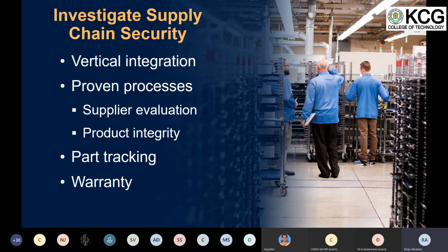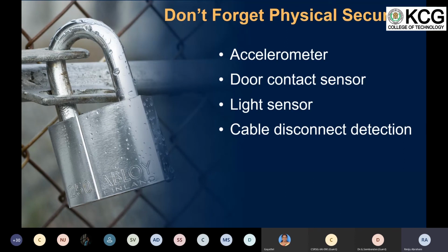Apart from the cybersecurity of internal devices, we should also follow physical security, like the perimeter, the physical fencing and all, and accelerometers in the devices. There are devices which have an inbuilt accelerometer, door contact sensor, and light sensor. These can detect such things and alert the operator or the engineer, and an alarm can be raised if any door of the panel is being opened, or if there's any shake in the panel. So these physical security features should also be considered a part of a cybersecurity system.